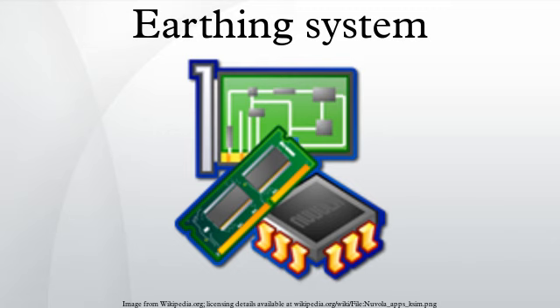IEC terminology: International Standard IEC 60364 distinguishes three families of earthing arrangements, using the two-letter codes TN, TT, and IT. The first letter indicates the connection between earth and the power supply equipment. T: a direct connection of a point with earth. I: no point is connected with earth, except perhaps via a high impedance.